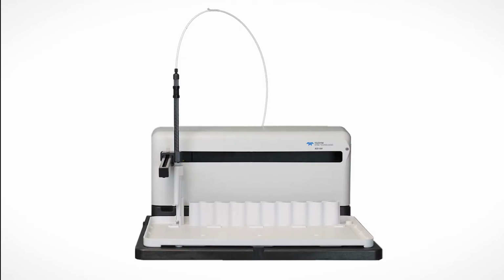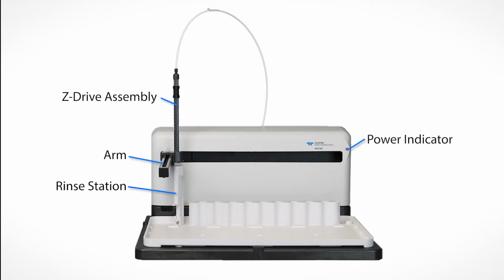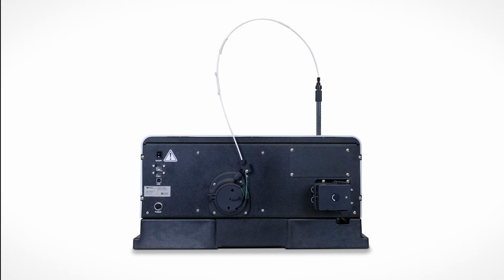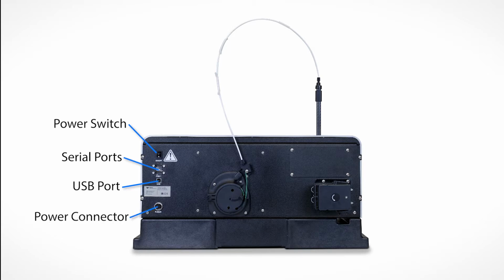Before you begin, familiarize yourself with the parts of the autosampler. In front are the Z drive assembly, the arm, the rinse station, the power indicator, the standards rack, and the sample tray. On the back are the power switch, the serial ports, the USB port, the power connector, the Z drive rotor, and the peristaltic pump.